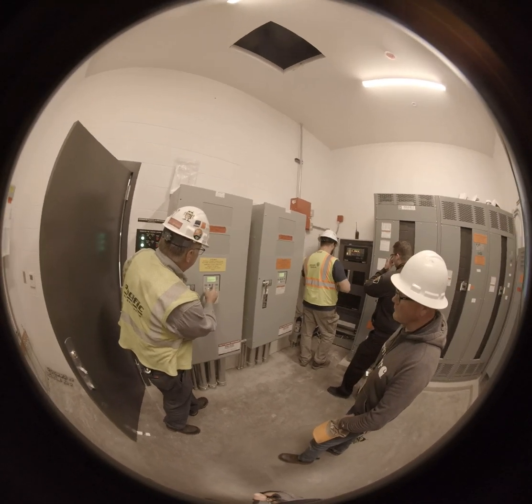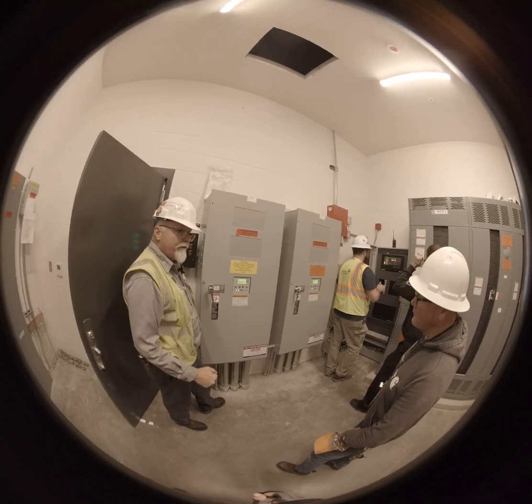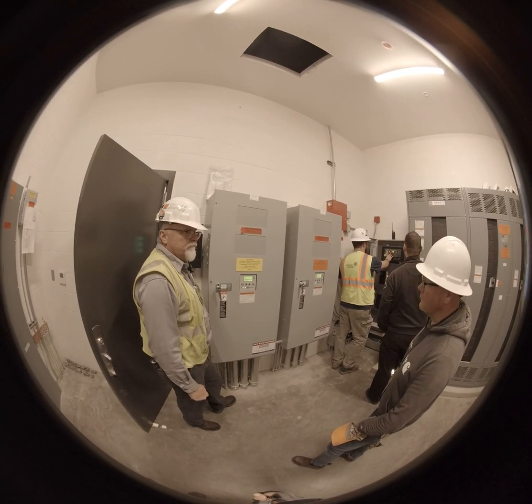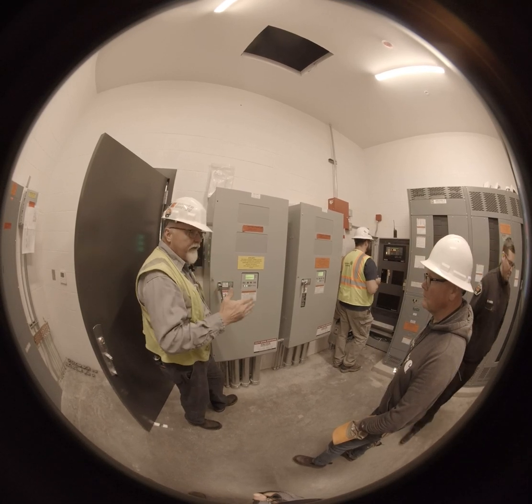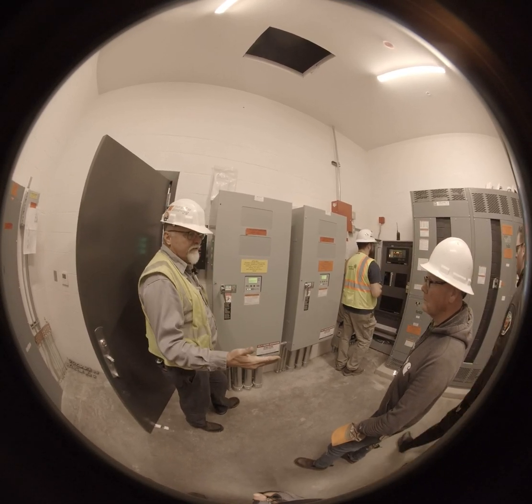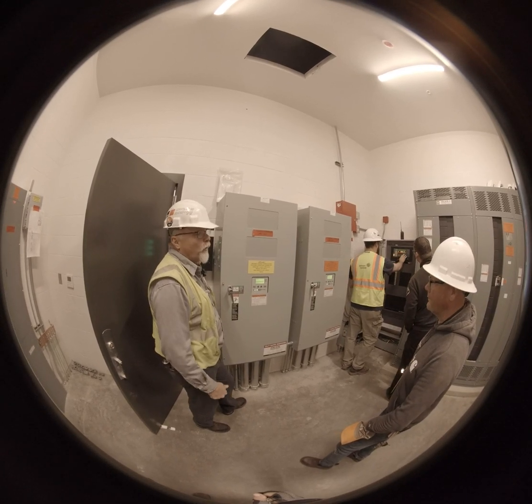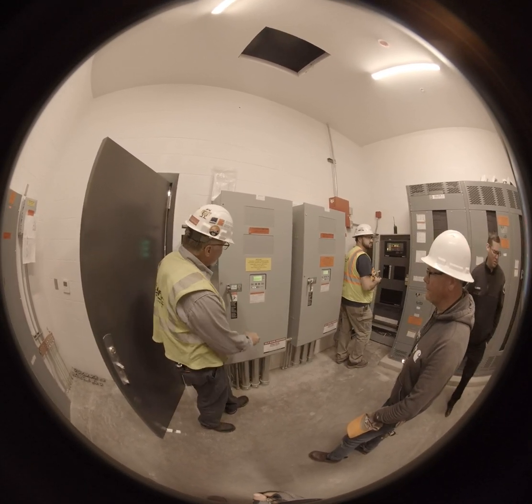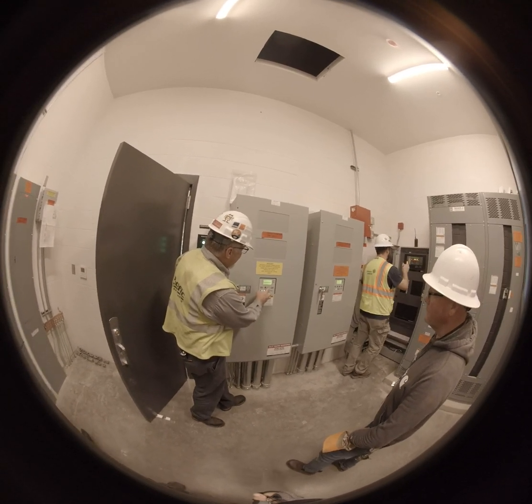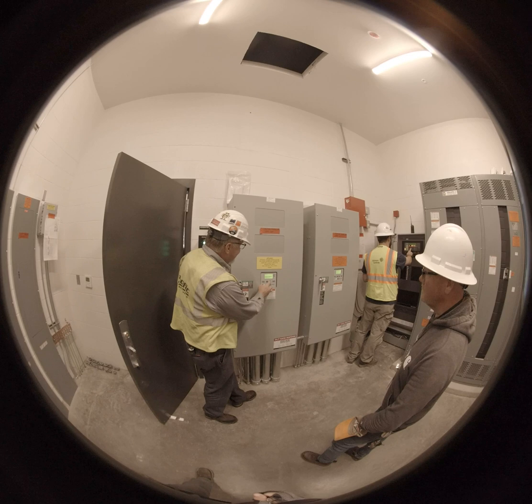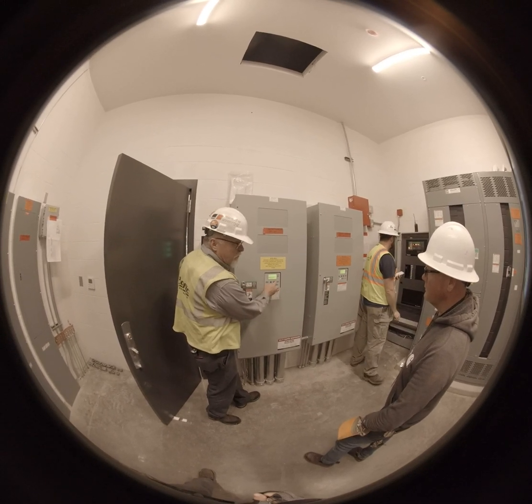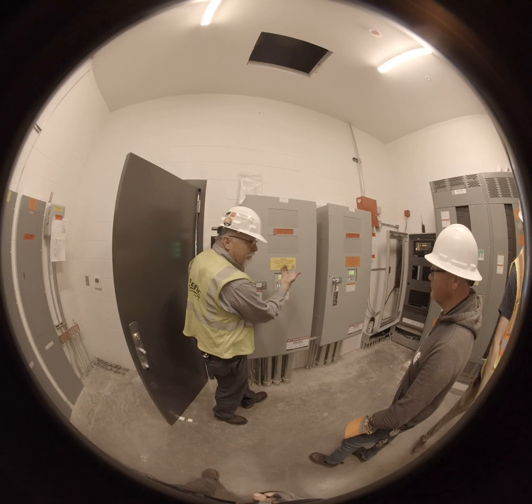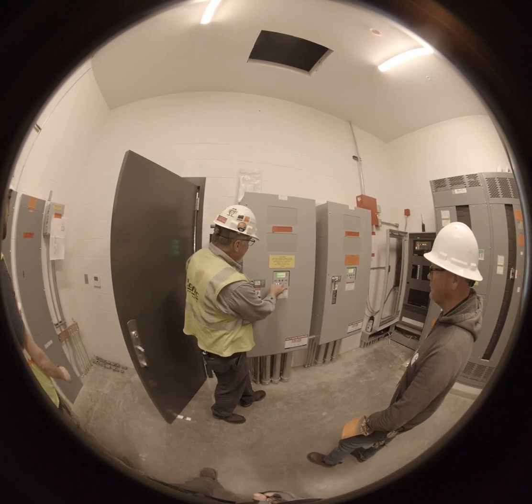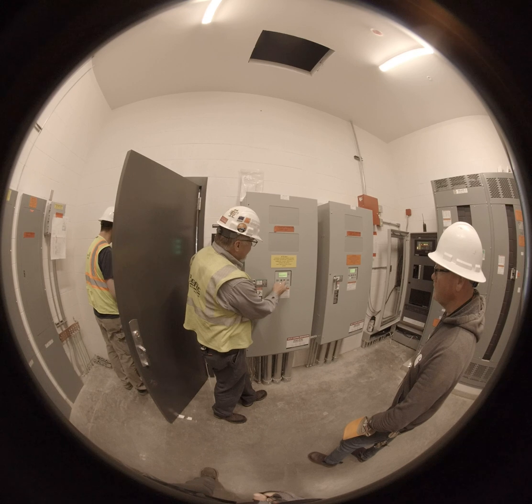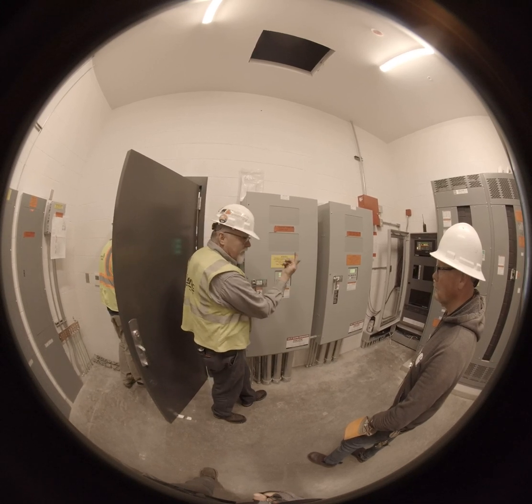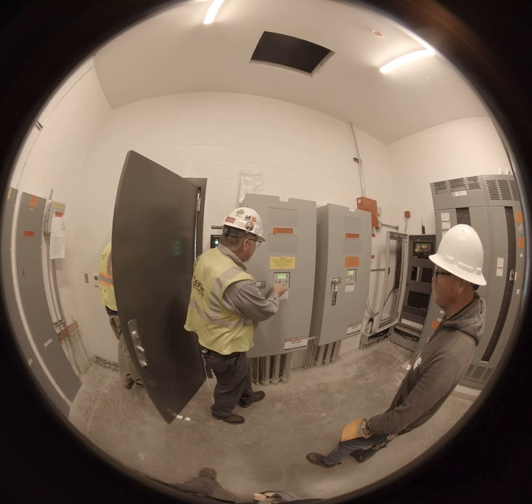And here's the other direction. Emergency back to normal. Again, it's 20 seconds. So in an outage, you're going to see that the elevator will shut down for that 20 seconds before it retransfers, or seek a floor and then shut down. Okay? And load disconnects, we don't use load disconnects on this. You can use them to shut motors down or whatever. Same idea as the elevators. Emergency acceptance fail: if it doesn't see emergency in 3 seconds, it's going to throw an alarm. And then back to the beginning.